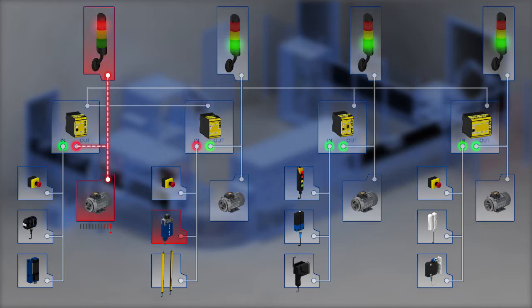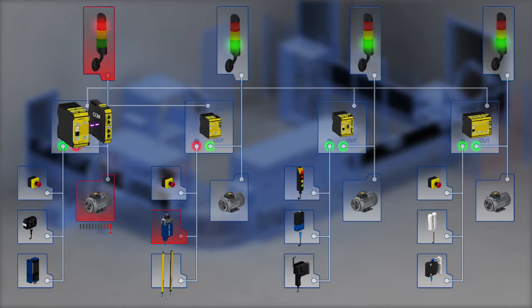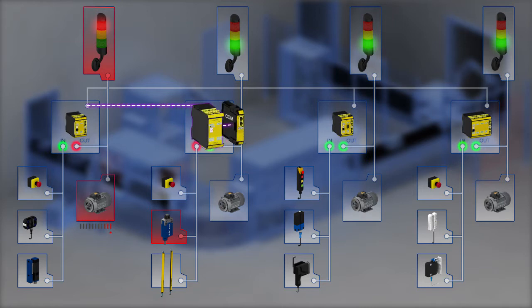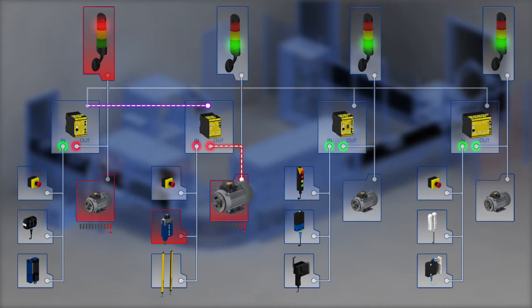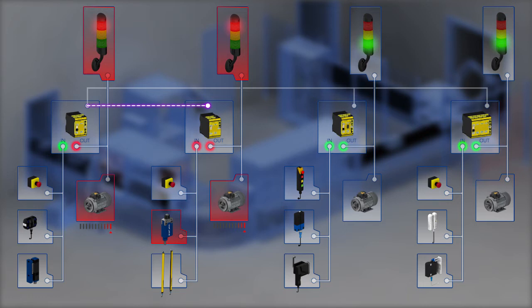The feeder process for system component 2 is shut down and the error is signaled via an indicator light. The detected fault 'sensor actuated' is at the same time transferred to the internal universal communication module. The communication module sends the command 'shutdown outputs' back to the remote I/O module. The motor is then shut down and the error is signaled via an indicator light. While system components 1 and 2 are shut down due to the open safety door, the downstream system components 3 and 4 can continue to produce.